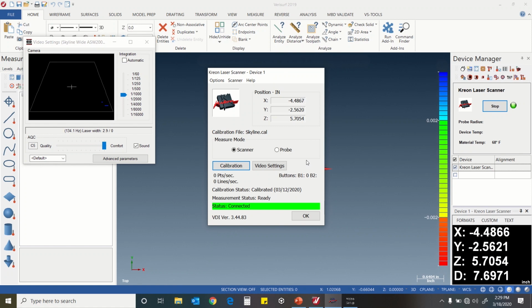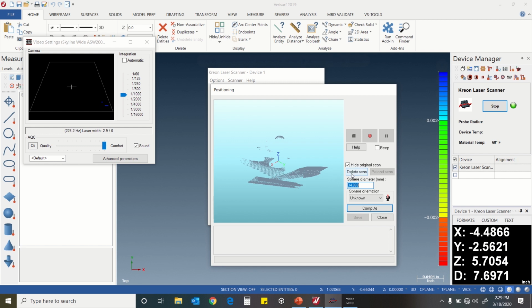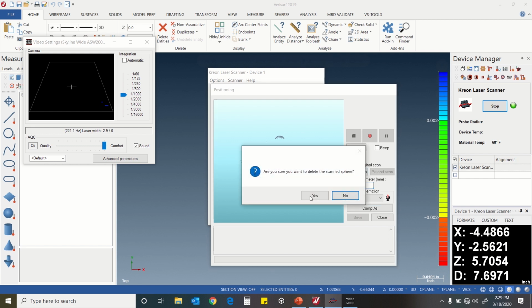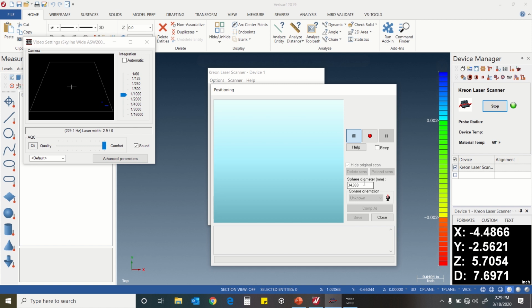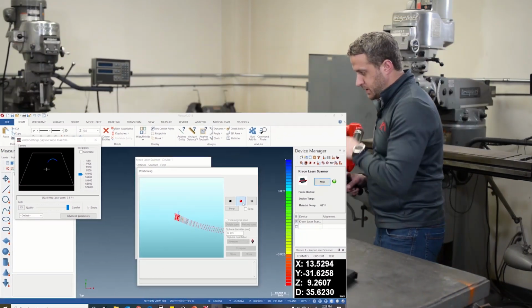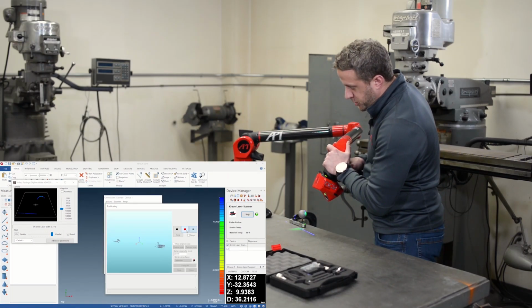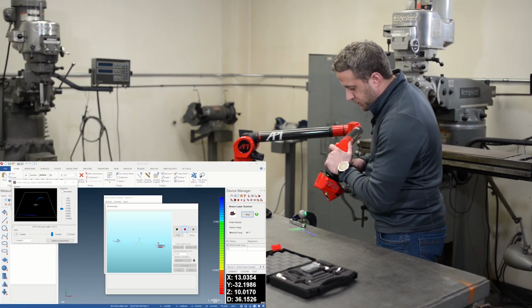So now that the arm is started, in our device controls, we're going to hit the calibration button. I have a previous scan in there, so I'm going to delete it out. And then it asks us here to put in the nominal diameter of the sphere, which is written on the side. That's 34.999 millimeters. When we're ready to record, we're going to hit the record button. And then we're going to trigger to gather data.